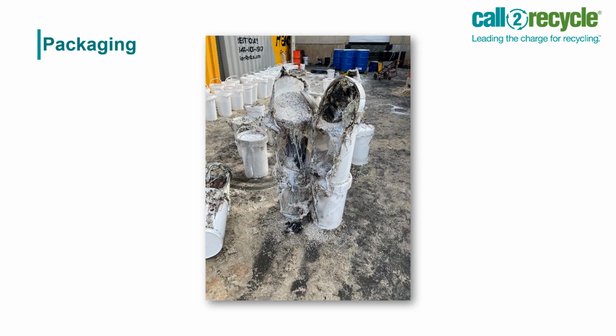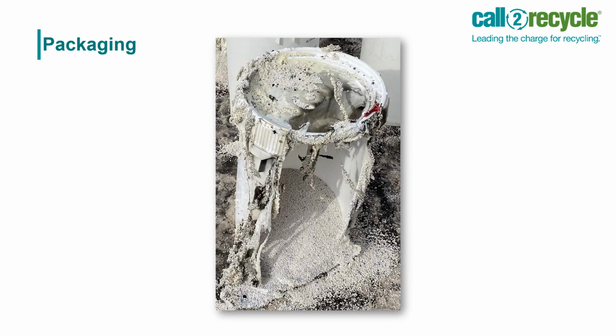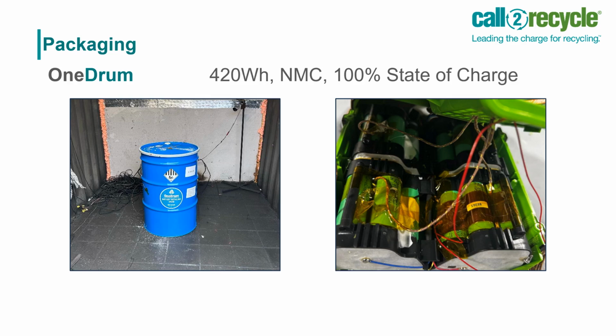You can see the battery melted right through the plastic before the fire suppressant had the opportunity to work. So what do we do at Call2Recycle when we work with ESA on these batteries? We actually test for containment, because containment is not a portion of the regulations.